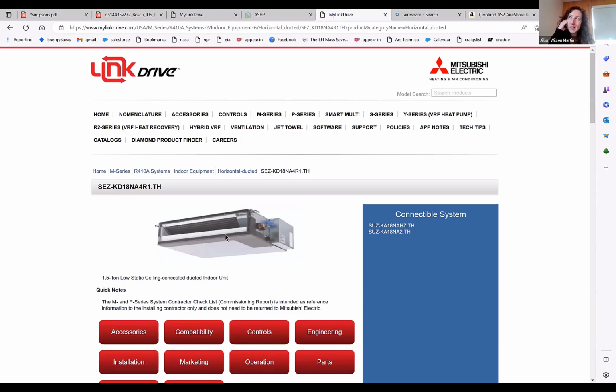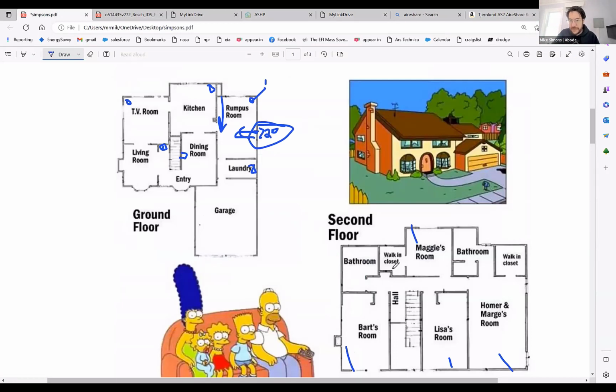Are the ducts more like that tubular, silver kind of thing—sheet metal flex duct? Yeah, usually we see the unit with a collar that splits it into 3 or 4 ports, and they pull flex duct to each room. This doesn't have as much pressure to push air through, so with this type of system on the Simpsons floor plan, they wouldn't have enough capacity to add a register into the bathroom, the walk-in closets, or centrally in the hallway.